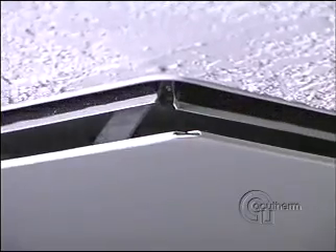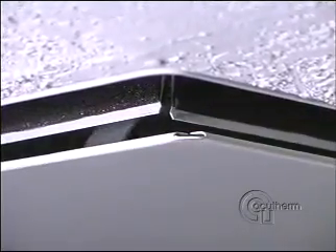We will be able to view these features through the use of both smoke injected into the supply air or primary air and infrared imaging. A brief puff of smoke injected into the supply air shows us how it enters the room. By using slow motion, we can see how the supply air clings to the ceiling. This is known as the Coanda effect.